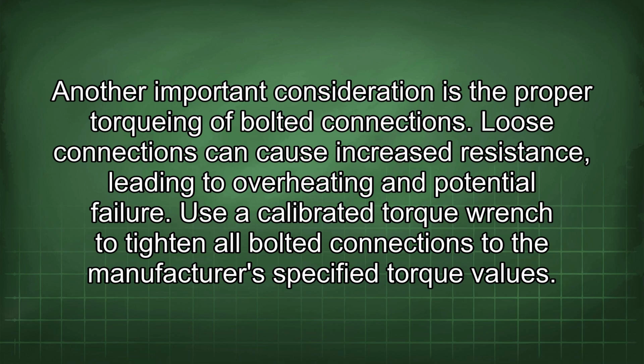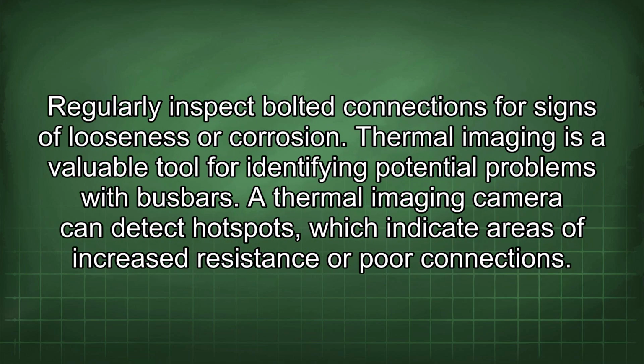Another important consideration is the proper torquing of bolted connections. Loose connections can cause increased resistance, leading to overheating and potential failure. Use a calibrated torque wrench to tighten all bolted connections to the manufacturer's specified torque values. Regularly inspect bolted connections for signs of looseness or corrosion.